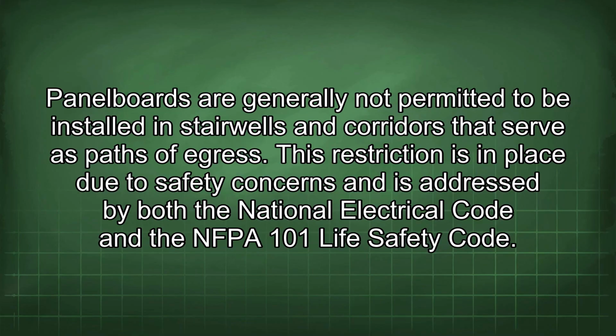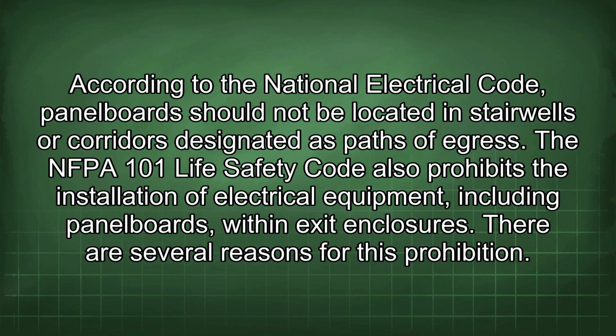Panelboards are generally not permitted to be installed in stairwells and corridors that serve as paths of egress. This restriction is in place due to safety concerns and is addressed by both the National Electrical Code and the NFPA 101 Life Safety Code. According to the National Electrical Code, panelboards should not be located in stairwells or corridors designated as paths of egress. The NFPA 101 Life Safety Code also prohibits the installation of electrical equipment, including panelboards, within exit enclosures.